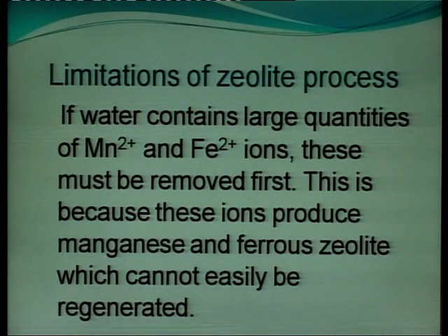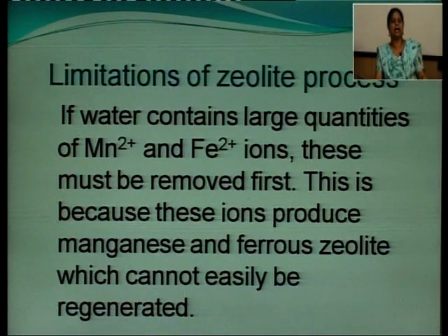Another limitation is that if the water contains high amounts of manganese and iron ions, ferrous ions, then this water can also not be treated through this process. The reason is that the manganese and ferrous zeolite which are produced by passing this water through the zeolite bed cannot be regenerated easily.